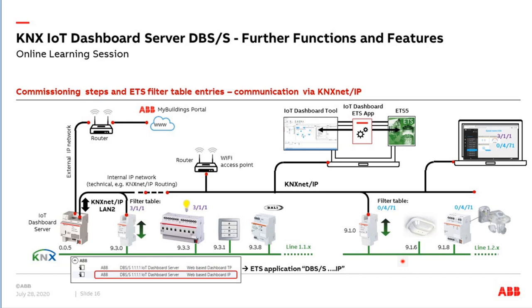Here is an example of filter table entries when using communication via IP. The IoT Dashboard Server communicates via LAN port 1 or LAN port 2 — in this example via LAN port 2. Via KNXnet/IP, it communicates to the IP routers and other devices. For example, group address 3.1.1 used for switching the light must be in the filter table, and group address 0/4/71 used locally is forwarded via KNXnet/IP so the status can be seen in the dashboard server. This happens automatically when you synchronize and download the filter table entries into the IP router.